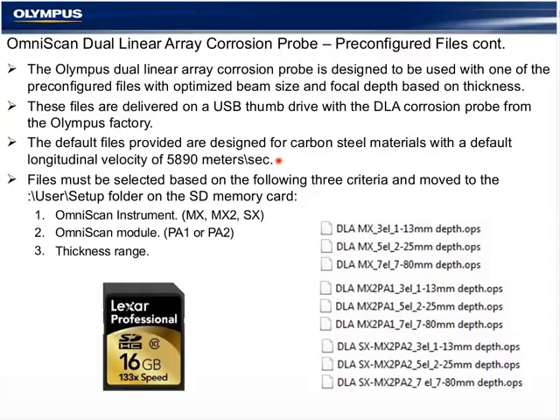The files are selected based on 3 criteria. The relevant file that you'll need to drive your probe is first based on the OmniScan instrument. So that's either a first generation MX, a black, smaller, non-touch screen OmniScan, the MX2, which is the blue base unit with a touch screen, or the new OmniScan SX. So depending on which of those instruments you have, we'll select the appropriate group of files. And then for the MX2, there's another group based on if your module is either the first generation PA1 or second latest generation PA2. And then within the three, for each of the possibilities, is a thickness range.